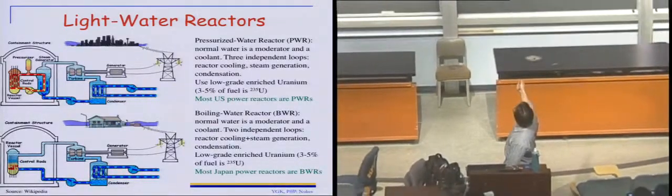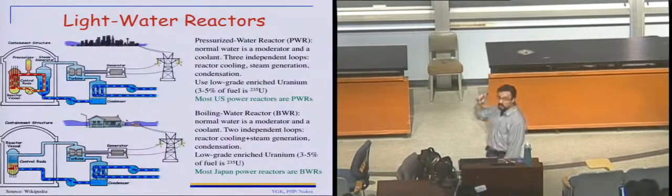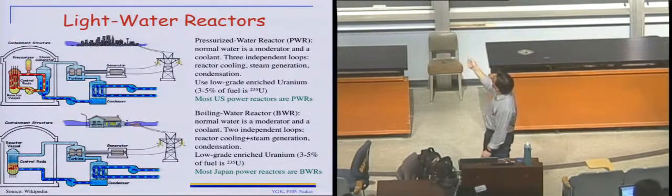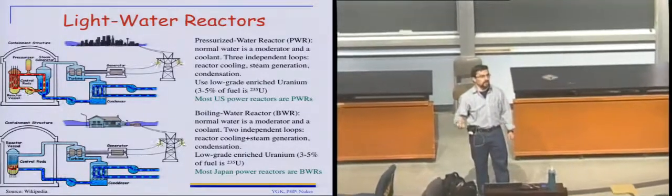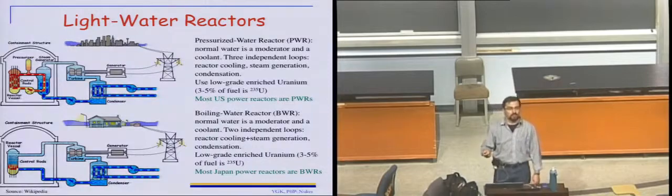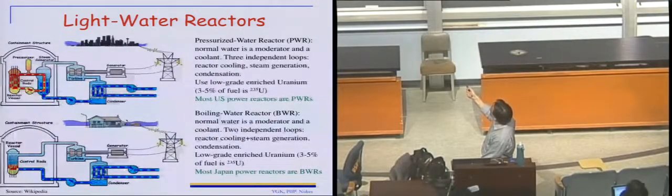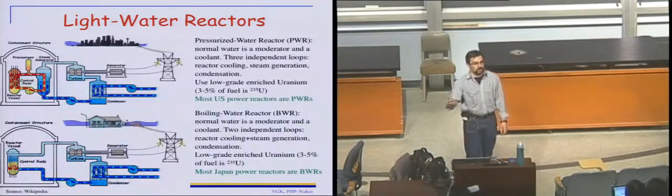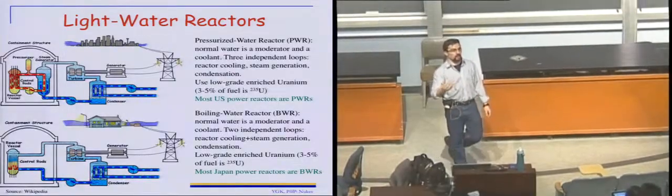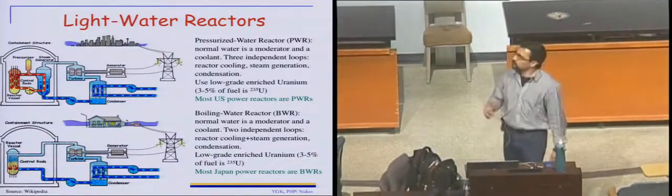So the normal pressurized water reactors have 3 loops that run the water for 3 different purposes. The inside loop that actually comes in contact with the nuclear fuel rods and therefore has a potential of being contaminated by radioactivity is contained in the first containment zone and is kept under pressure. It's circulated through the reactor core, and it primarily works as the moderator to slow the neutrons down and to actually increase the reaction rate, and it is also used to cool the reactor core to remove energy from it.